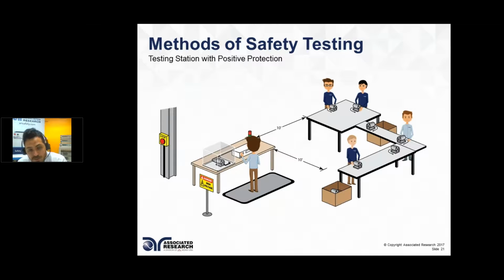Also, OSHA regulation says that if the employer does not consider the employee trained or qualified to handle those high voltage instruments, then there needs to be a 10-foot barrier so they don't get near that instrument. Now, it's you who decides who's qualified or not. So again, the onus falls on the manufacturer to label someone as qualified or not qualified.